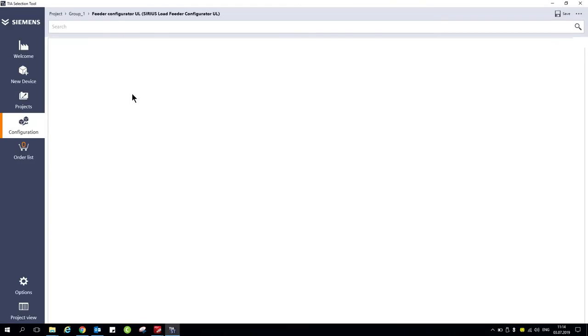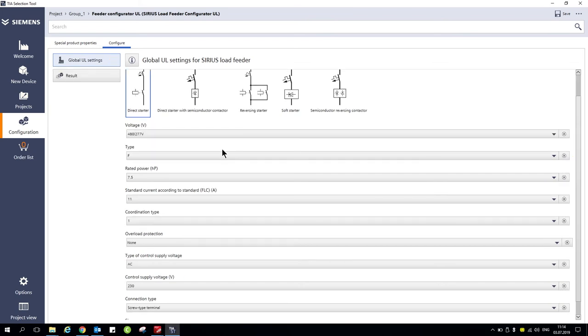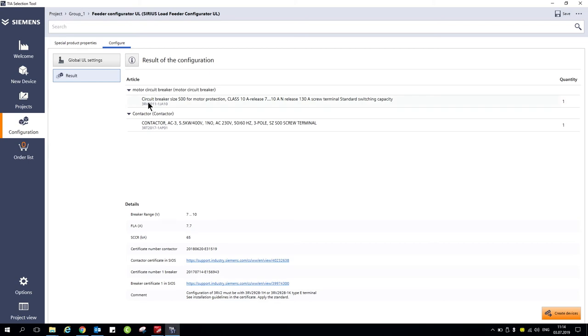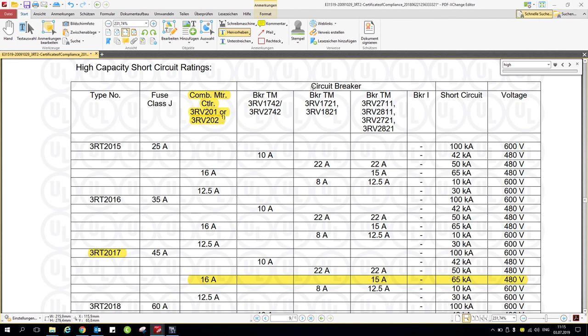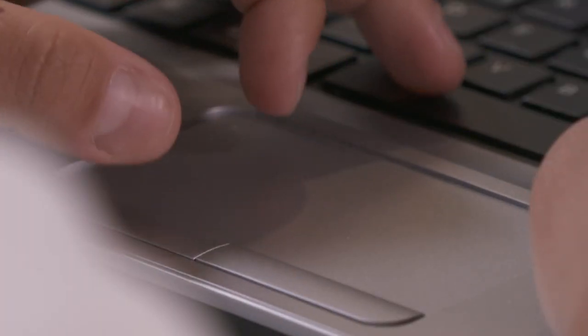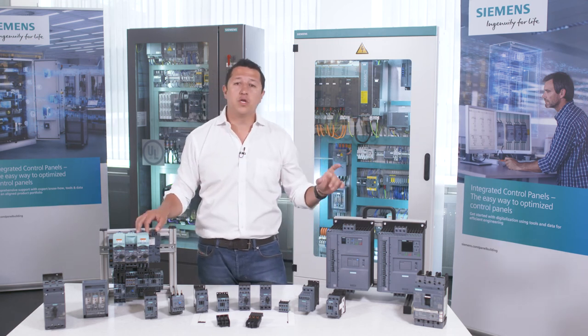In the case of selecting the UL configurator, you also click Configure and make a selection the same way. Once the selection is complete, the result tab pops up. When you click Result, the motor circuit breaker and contactor are also displayed, and you can find the certificates under Siemens Industry Online Support. When downloading the UL certificate of the contactor, you can find the high short circuit current ratings. In this table, you can see that the contactor selected, with the combination motor controller 3RV20, has a range up to 16 amperes where you can have a short circuit capacity of 65kA. The IEC certificate has a proven combination, and this cannot be changed — if a different product is used, the short circuit capacity is not the same.